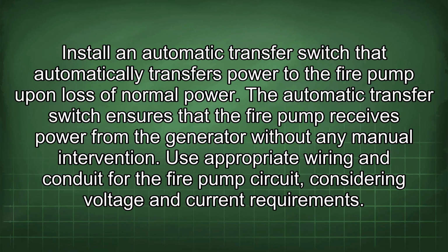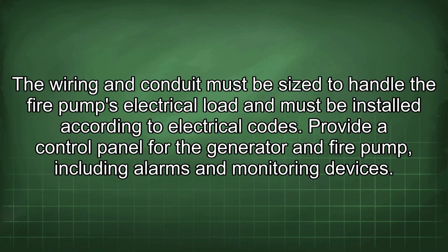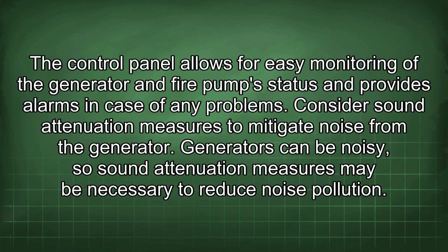Use appropriate wiring and conduit for the fire pump circuit, considering voltage and current requirements. The wiring and conduit must be sized to handle the fire pump's electrical load and must be installed according to electrical codes. Provide a control panel for the generator and fire pump, including alarms and monitoring devices. The control panel allows for easy monitoring of the generator and fire pump status and provides alarms in case of any problems. Consider sound attenuation measures to mitigate noise from the generator. Generators can be noisy, so sound attenuation measures may be necessary to reduce noise pollution.